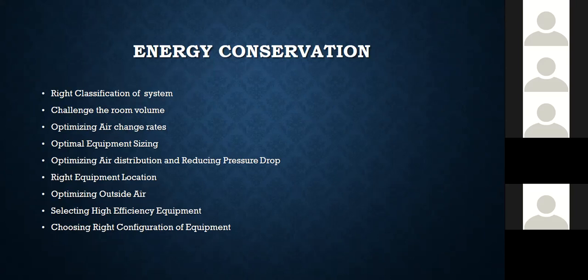As I told you, energy conservation is a very important topic, a very interesting topic also. Starting from the beginning, you should go for the proper classification, what type of system you need. So from that time, in the pre-concept stage itself, you should focus more work and you should classify it properly. Then you also should consider the room volume, basically the ventilation rate, where you have, because like I was telling, 100% fresh air, how much return you are going to take. So in that, you have a lot of opportunities to reduce the load.